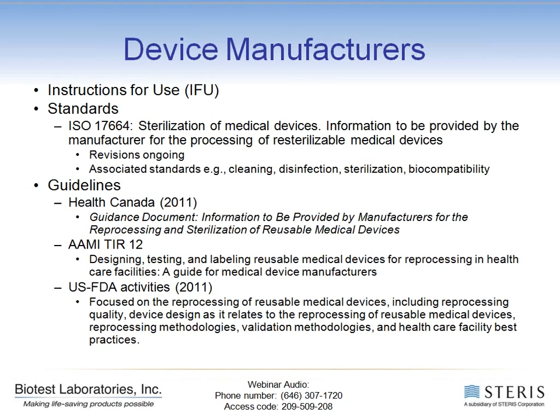And then we have specific guidelines. For example, Health Canada have a guidance document really reiterating the same information. The AAMI TIR 12, which has been in place for a number of years. And then we've even had a great focus on this from the FDA in 2011, which really focused our attention on this area. And many of you may be familiar with this draft guidance for industry and FDA staff regarding reprocessing of devices and the validation of methods and labeling requirements to include instructions for use. This has become essential for 510K applications in the United States. And I've already mentioned that if this is not done correctly, this can lead to rejection by the FDA.